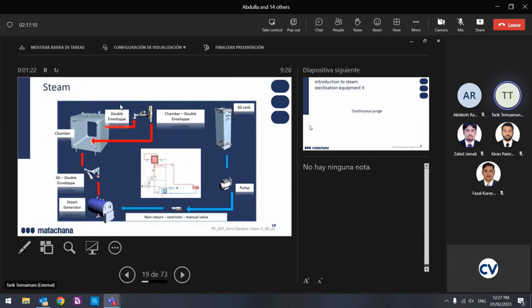This line is coming from the heat exchanger. What I told you, after the sterilization plateau, we remove the water and condensate from the chamber, but we don't put it directly into the vacuum circuit because of the water consumption. So we use a heat exchanger. It has two lines, one cold and one hot, and mixing them cools the hot water and heats the cold water. Then we get colder water in our steam sterilizer.